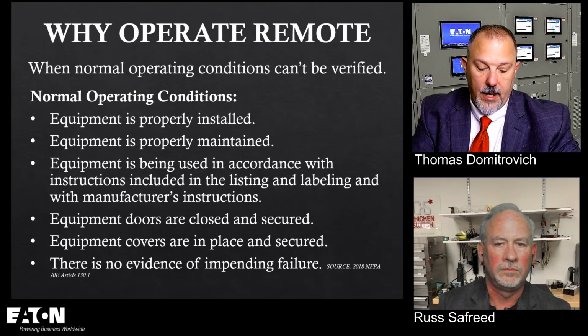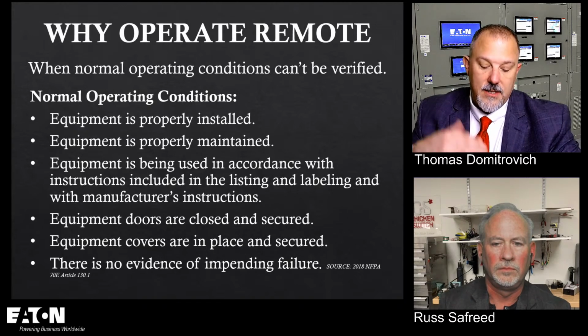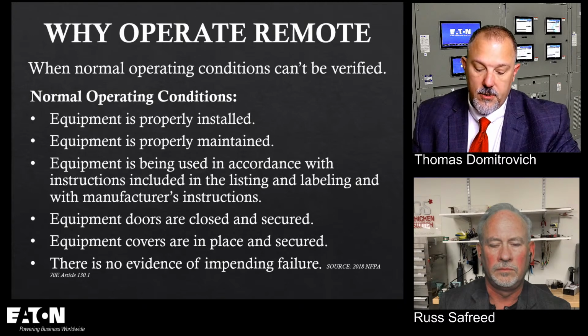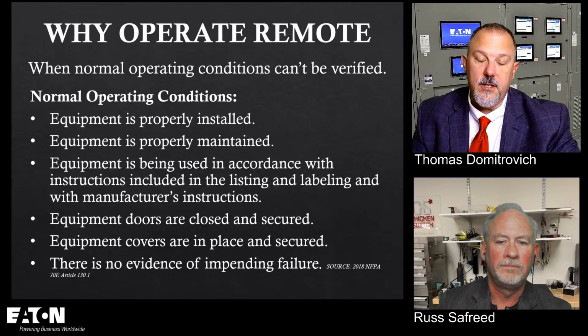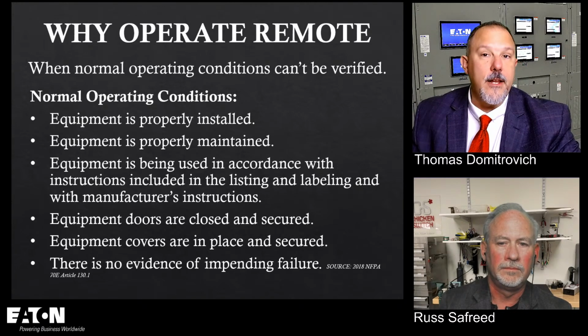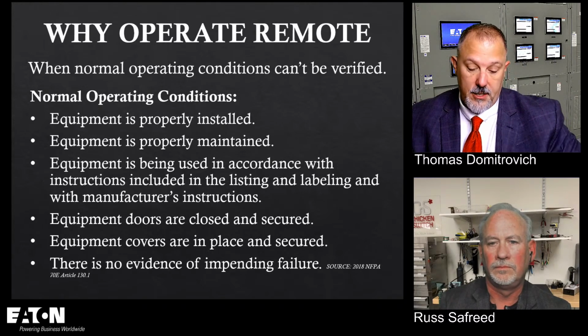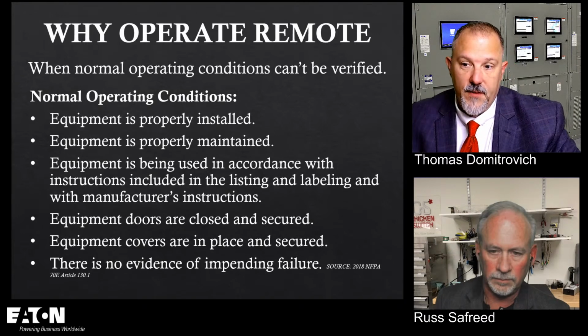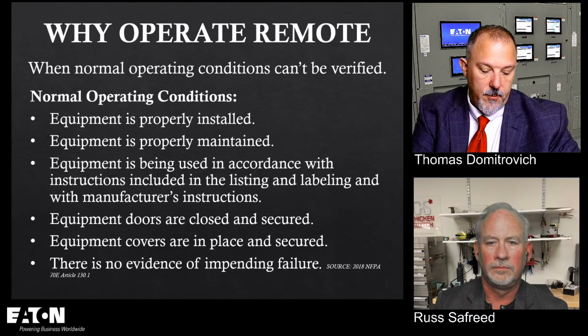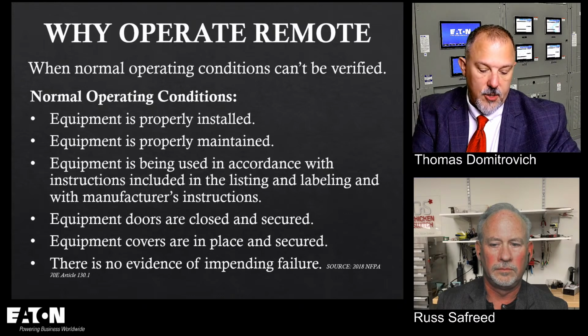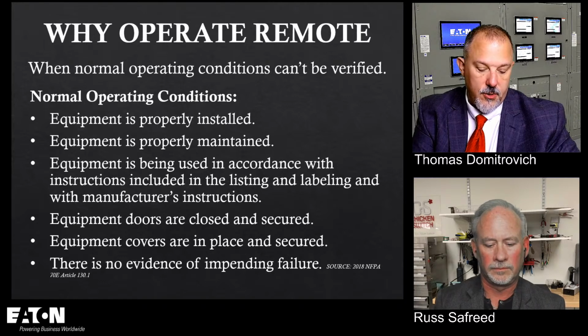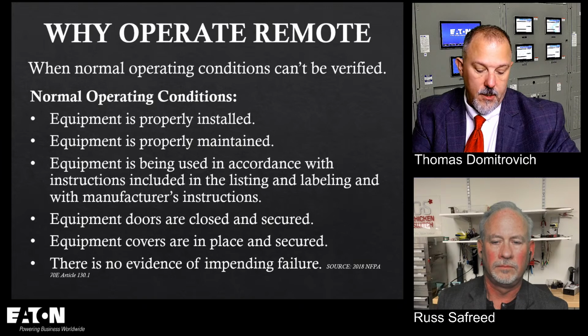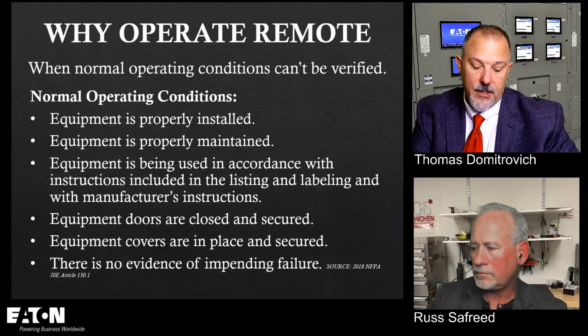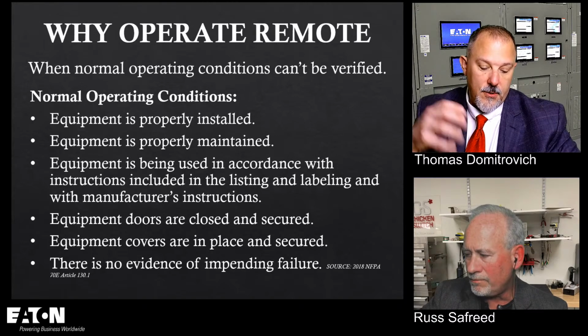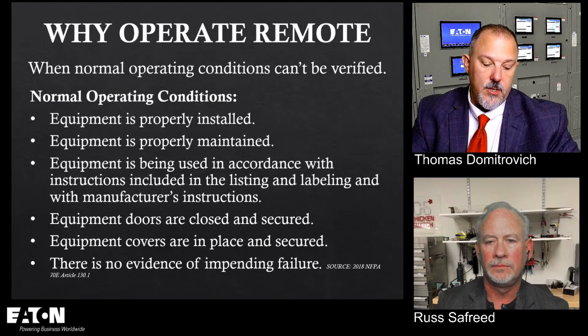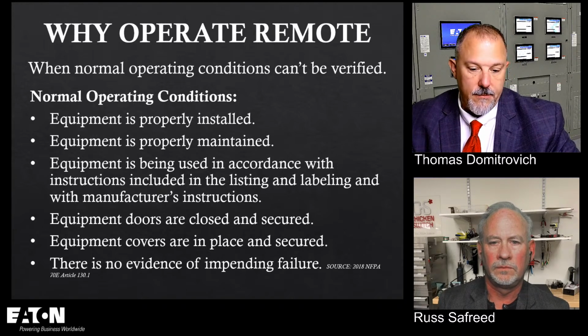Insertion or removal of plug-in devices, the busway, examination of insulated cable. It goes down through all of these lists, examining voltage transformer or conductor, control power transformer compartments. It gives you all of these conditions, and it basically tries to give you an estimate of whether there is a likelihood. Then you have to figure out severity, which is your arc flash calculations, and then obviously voltage if it's 50 volts or more. Now, insertion or removal of covers for DC systems, opening voltage transformers, operation of a circuit breaker, switch, contactor or starter, voltage testing on individual battery cells, opening a panel door, hinged door, or cover to access dead front. So there's a lot of things in here that help you in determining the likelihood of the occurrence.